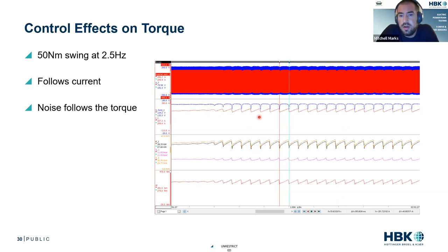2.5 hertz rate. We're ramping current at a 2.5 hertz rate. We see power and reactive power ramped at a 2.5 hertz rate. And if we look at torque in red, we see at 2.5 hertz, we have a 50 newton meter swing. This is absolutely exciting to the structure. This is absolutely creating noise and vibration.